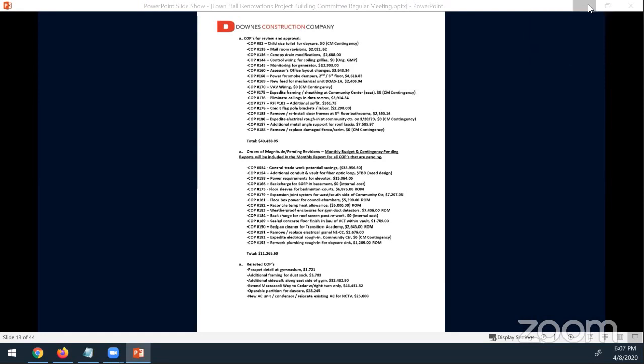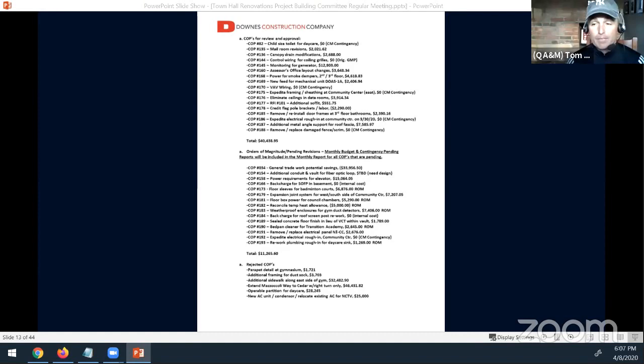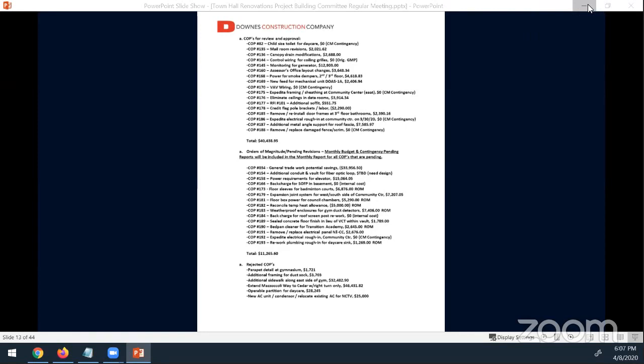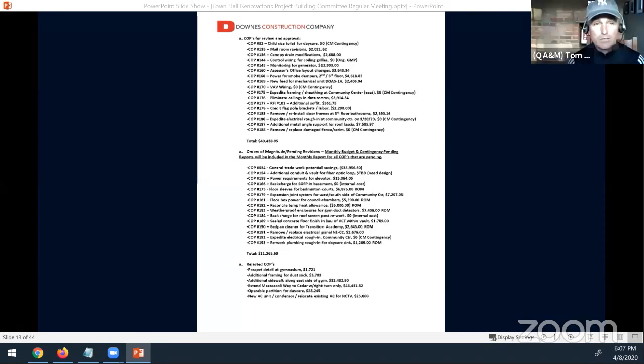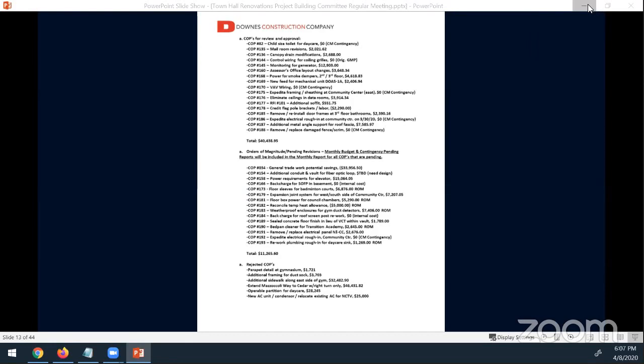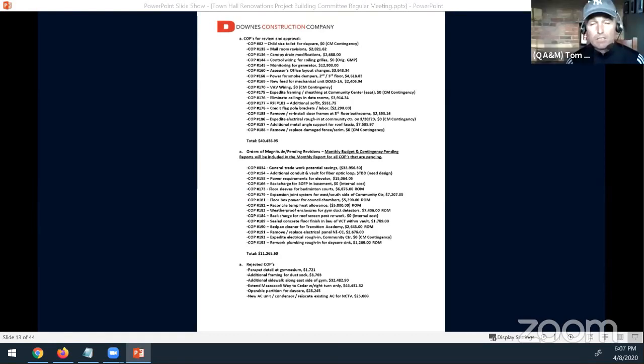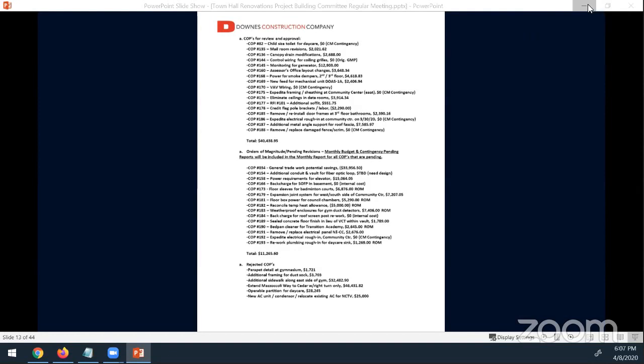Essentially that means there would be no heating, cooling in the gym. When the generator is running, there's a huge load associated with that RTU. It's about 12% of the total load. So if we back that RTU off the generator, that brings us to 75% of calculated load.